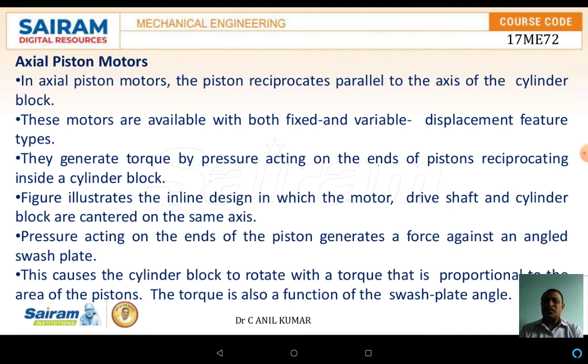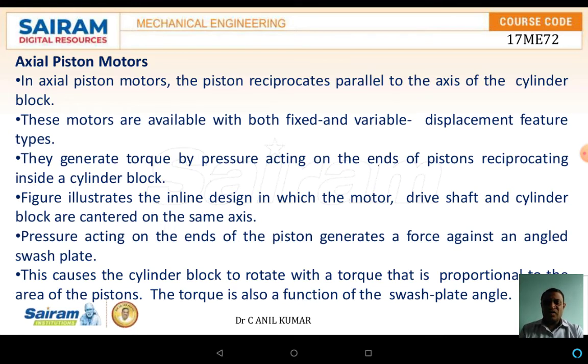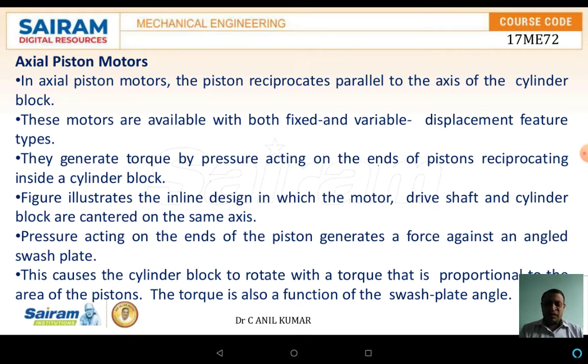In the axial piston motors, the piston reciprocates parallel to the axis of the cylinder block. These motors are available in both fixed and variable displacement configurations. They generate torque by the pressure acting on the end of the piston reciprocating inside the cylindrical block. The figure illustrates the inline design in which the motor, the driving shaft, and the cylindrical block are centered on the same axis. The pressure acting on the end of the piston generates force against the angled swash plate to rotate, causing the cylindrical block to rotate with a torque proportional to the area of the piston.